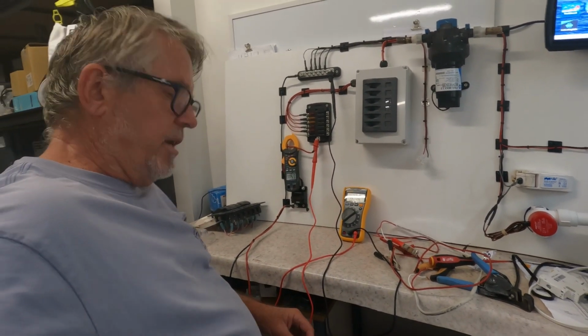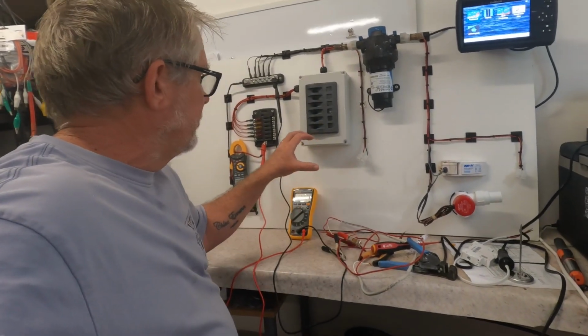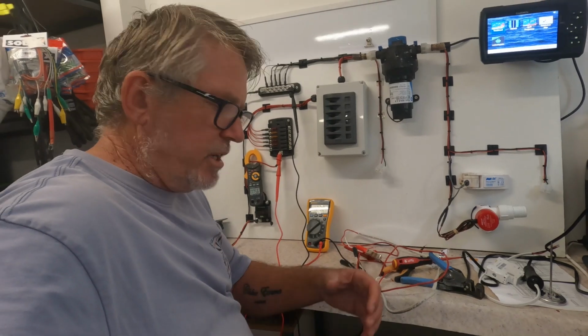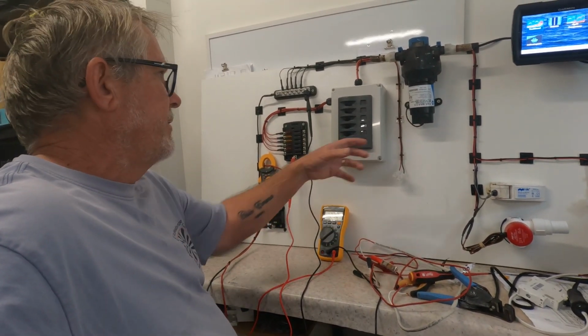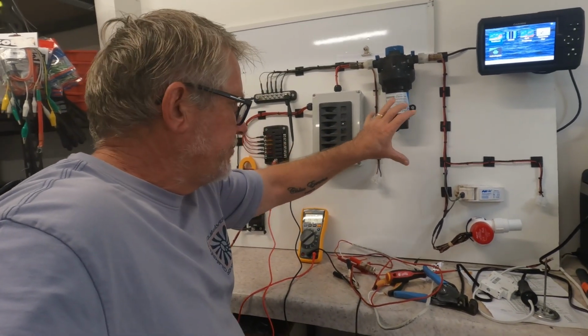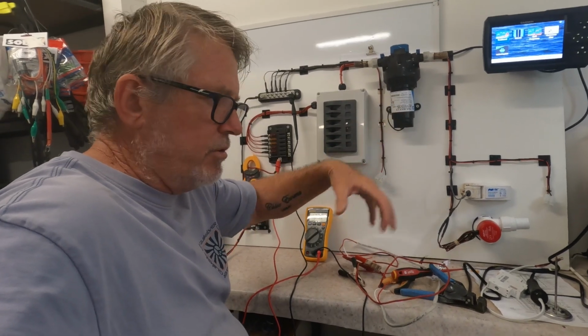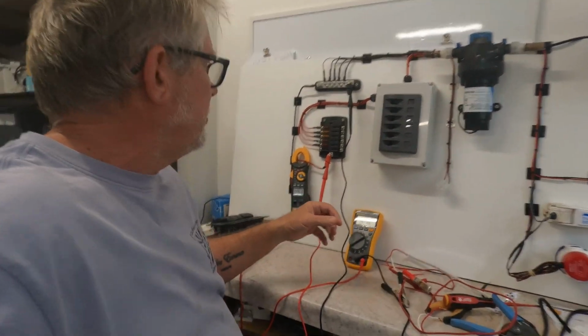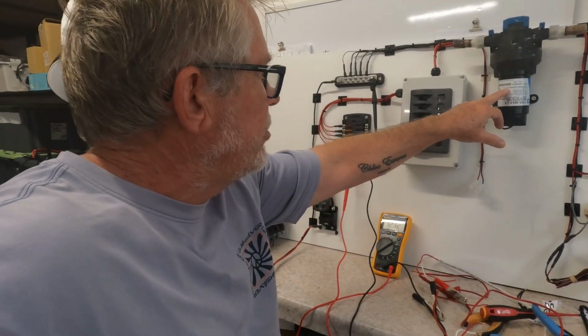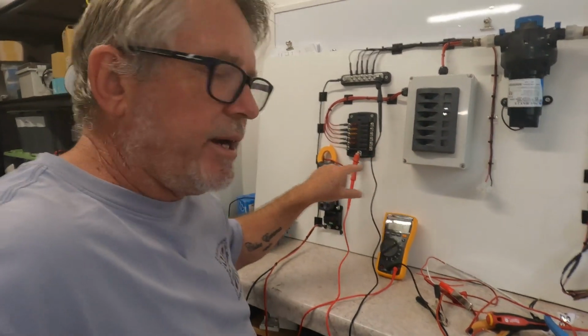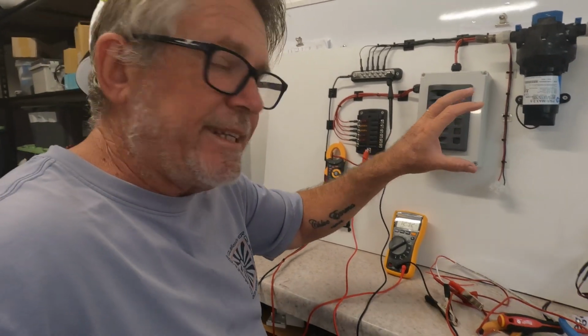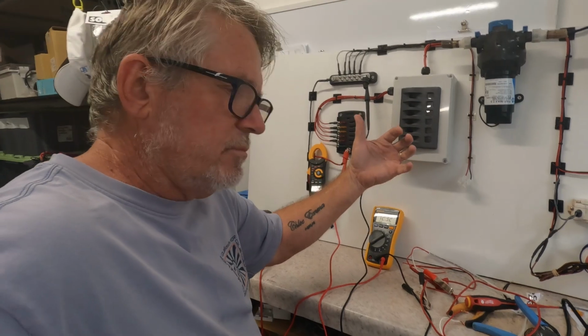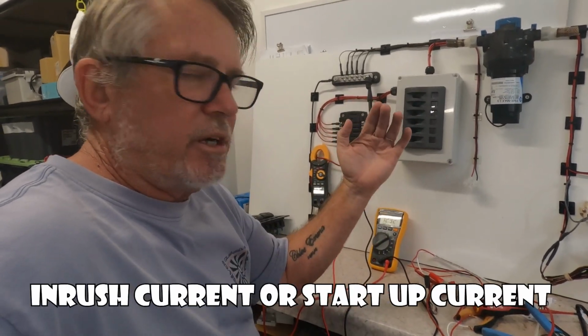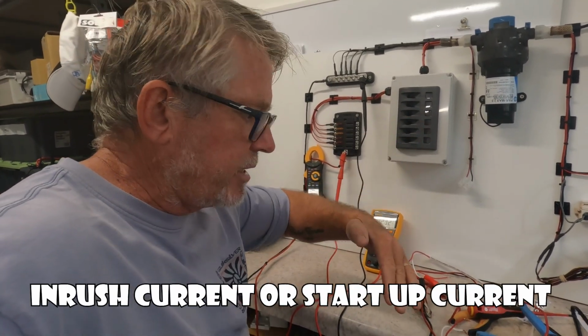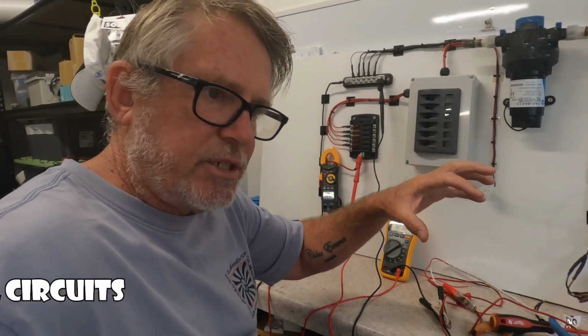Something I should explain: a lot of devices have what's called an inrush current, due to the inbuilt circuitry, and it varies device to device. When we first turn our pump on, watch how the current is affected. Hopefully we'll see an inrush current spike for a split second before it settles down to its normal operating load current.